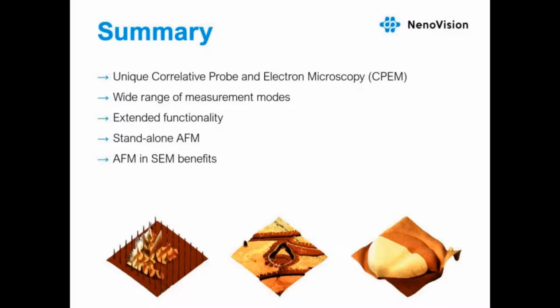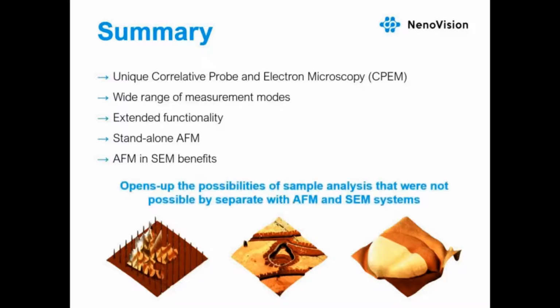If you want to, you can use LiteScope as a standalone AFM, and by integrating AFM and SEM, you will strongly enhance the capabilities of both techniques. It's simply better than using separate AFM and separate SEM. You can take advantage of the accurate AFM tip navigation to the region of interest by SEM, which will make your measurement extremely time efficient, and the whole time you work in in-situ conditions, which is crucial for sensitive samples. And importantly, it opens up possibilities of sample analysis that were simply not possible by separate AFM and SEM systems.